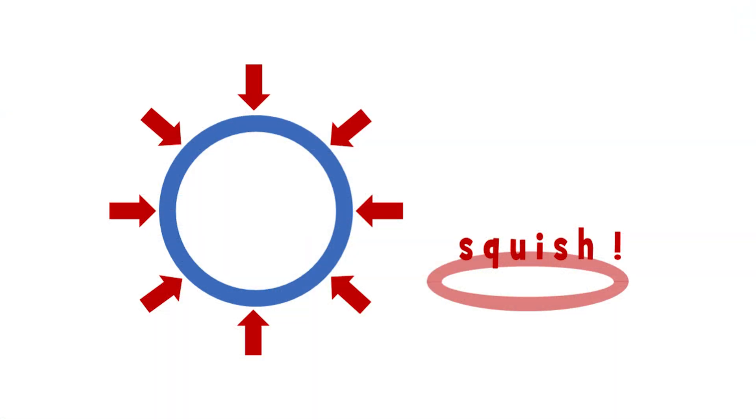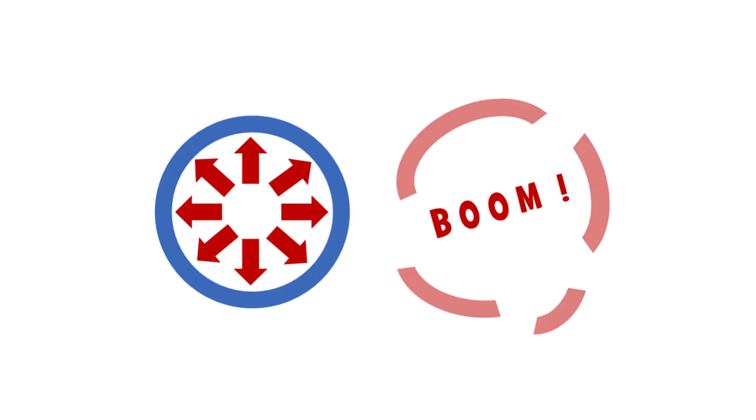Ductile iron pipe design is based on a three-prong approach, taking into consideration external earth load, which includes bending stress and barrel deflection, the live load a pipeline will be subjected to, traffic above the main, and the maximum internal pressure the pipeline is expected to encounter. The appropriate class of DI pipe is selected based on the worst-case scenario of these three design criteria.